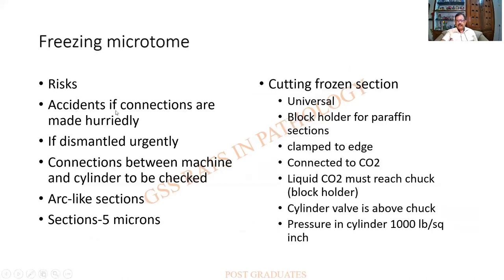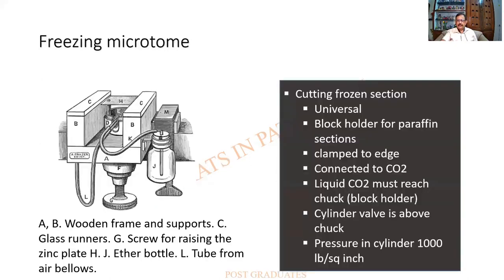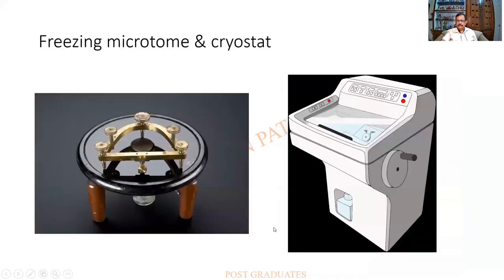The risks with the freezing microtome include accidents — not by mechanical cutting, but from the gas cylinders, which can cause great damage. Sections will be thicker than 5 microns. The instrument should not be dismantled in a hurry; great care should be taken after the procedure. Parts include a wooden framework, a block holder, a carbon dioxide cylinder with a tube, and the knife.